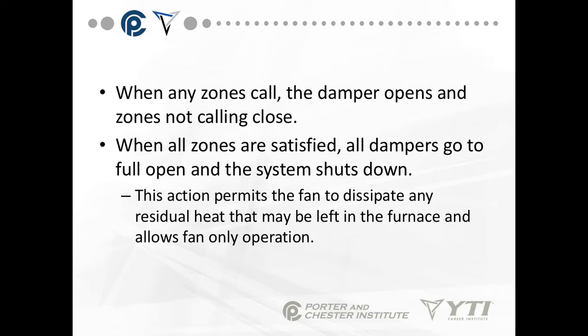When any zone calls, the damper opens for that zone and the zones not calling close. When all zones are satisfied, all dampers go to a fully opened position and the system shuts down. This action permits the fan to dissipate any residual heat that may be left in the furnace and allows fan-only operation.